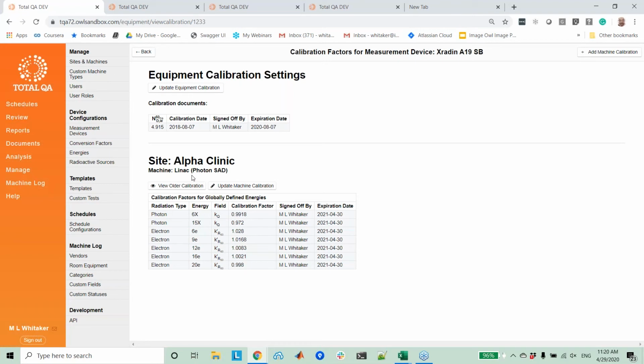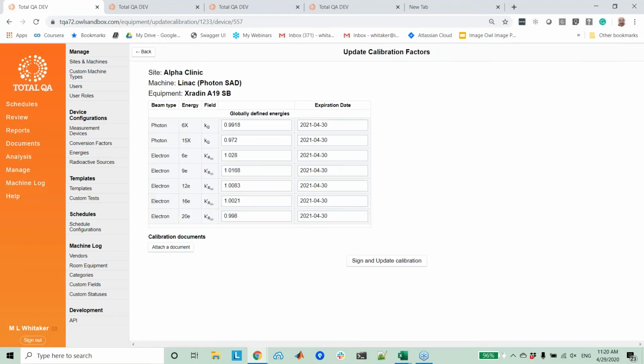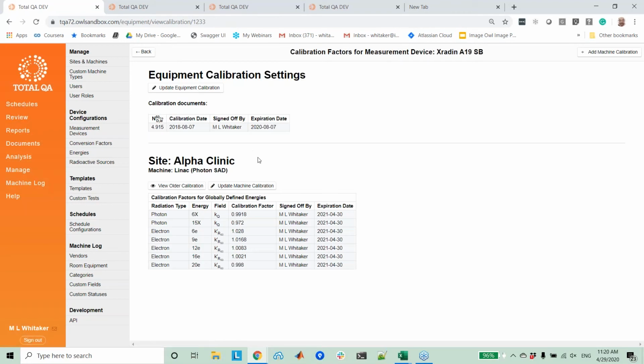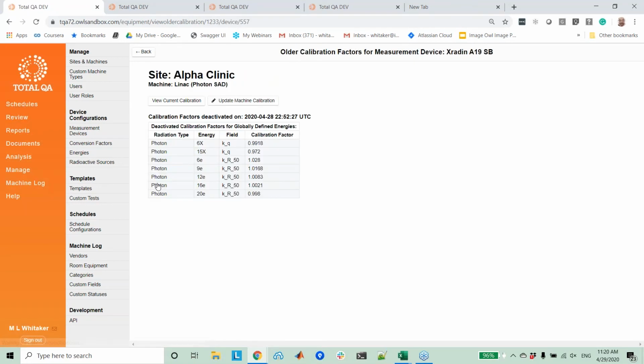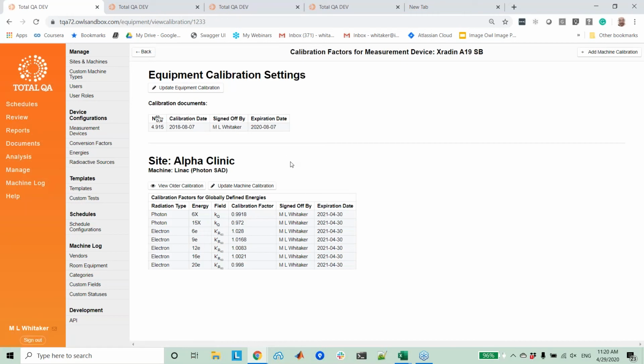So here I've set it up associated with this machine, and you can set up multiple machines with the one ion chamber. You're going to be setting up the KQ factor here for the photons, and then the K prime R50 factor for the electrons. And again, you put them in, sign off on it, and they're updated.